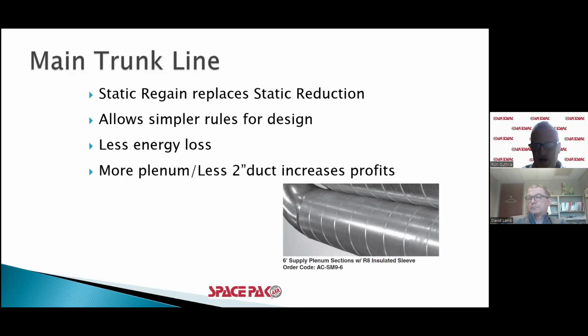That provides rigidity and also seals it further if there's any kind of leak through there, dirt in there, on the gasket, etc. All right, so less energy loss, more plenum, less 2-inch duct. Okay, so we always run more plenum, and if we need to, because we've got that 250 feet to work with, we run more plenum, and then we run less of the 2-inch duct.